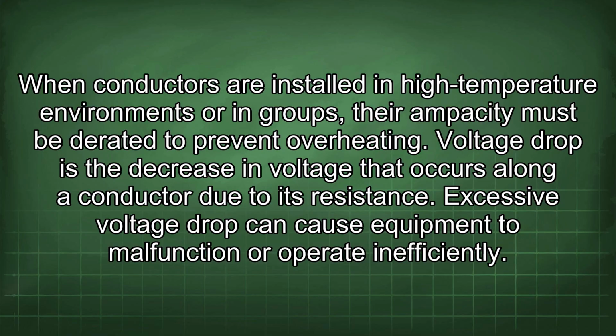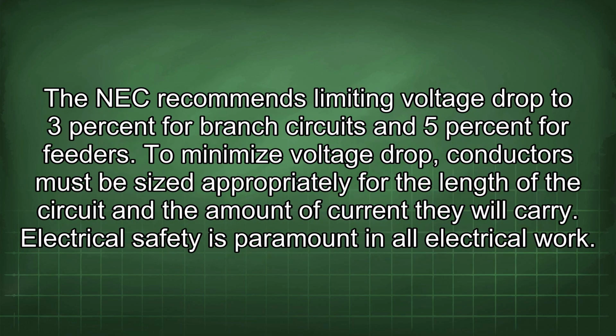Voltage drop is the decrease in voltage that occurs along a conductor due to its resistance. Excessive voltage drop can cause equipment to malfunction or operate inefficiently. The NEC recommends limiting voltage drop to 3% for branch circuits and 5% for feeders. To minimize voltage drop, conductors must be sized appropriately for the length of the circuit and the amount of current they will carry.